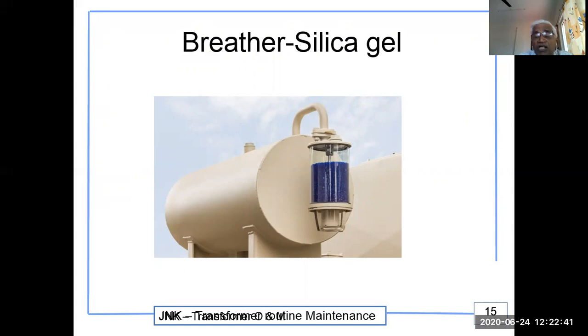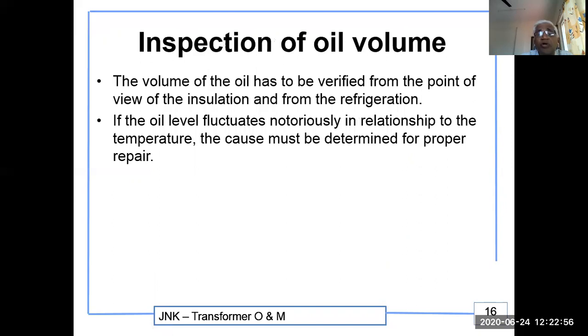And in the bottom, you can see one plastic cup also is there. You have to fill it with transformer oil till the marking is given. That is for filtering the dust coming through the air. And now inspection of oil volume. The volume of the oil has to be verified from the point of view of the insulation and the refrigeration. If the oil level fluctuates noticeably in relationship to the temperature, the cause must be determined for a proper repair.